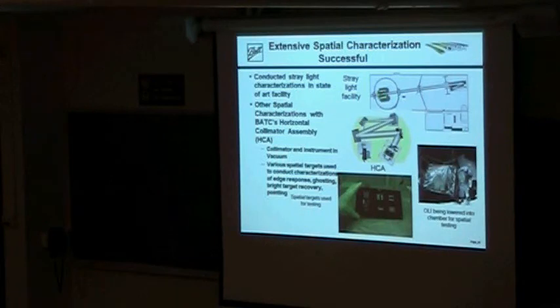So we actually have a collimator assembly we call the HCA, horizontal collimator assembly, that is used to measure this. It actually goes inside of a vacuum chamber. So this whole piece of test equipment goes inside of a vacuum chamber, all right? Here is the OLI instrument right here. We have the targets here for measuring these responses on this stage. It has to be folded around inside the chamber to an off-axis parabola. That's a collimator that's actually off-axis that then collimates the light that's directed into the instrument for these measurements. And we can scan the instrument back and forth to look across the field of view and so on. This is some of the patterns that we use that's set up here to focus of that collimator that we projected into the instrument for measuring these things.